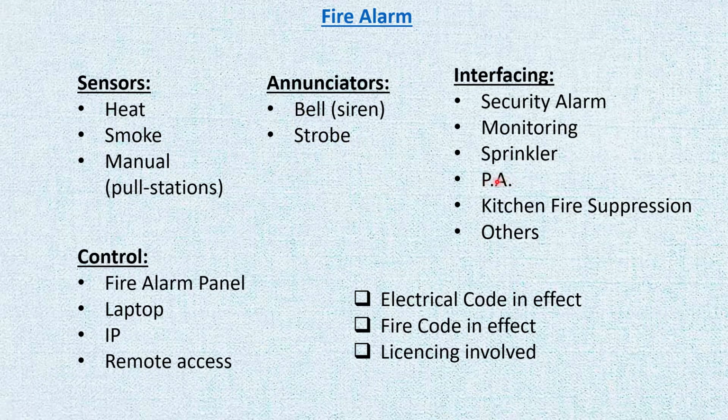But that will be within the interfacing. What do the fire alarms interface with? They interface with the security alarm, and vice versa. The security alarm can interface with the fire alarms. As far as monitoring, the fire alarms are not connected to the fire stations, the same as the security alarms are not connected to the police stations. All is connected to the monitoring station, and guess what? It will be the same monitoring station that you would use for the security alarms.